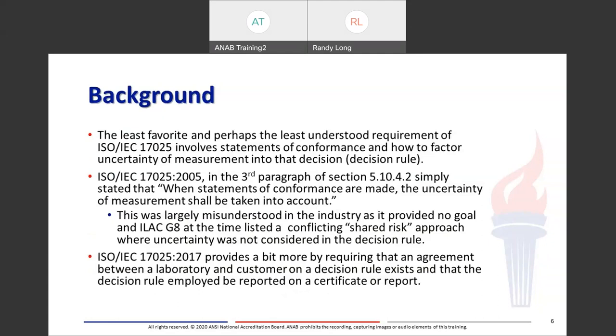The least favored and perhaps least understood requirement of 17025 involves statements of conformance and how to factor uncertainty and measurement into that decision — or what's called a decision rule these days. In 17025:2005, it was a very vague statement: 'When statements of conformance are made, the uncertainty of measurement shall be taken into account.' This was largely misunderstood in the industry as it provided no goal, and ILAC G8 at the time listed a conflicting shared risk approach where uncertainty was not considered in the decision rule.